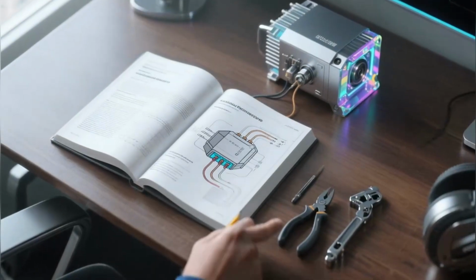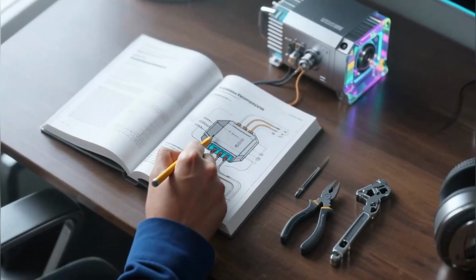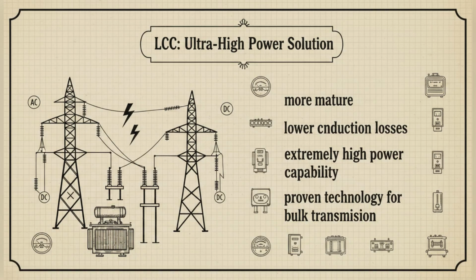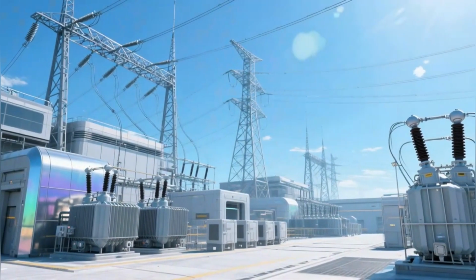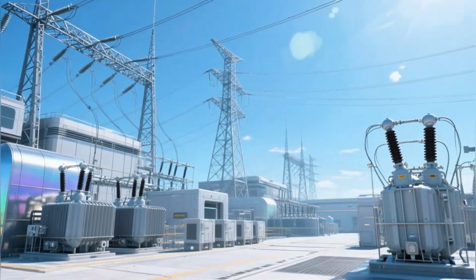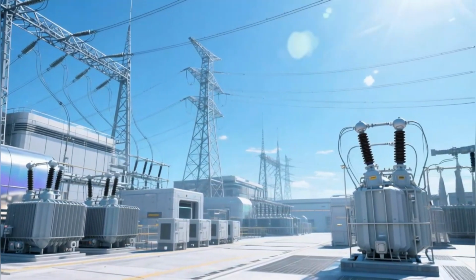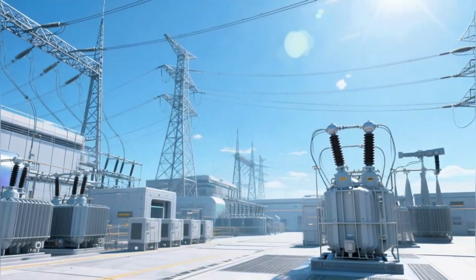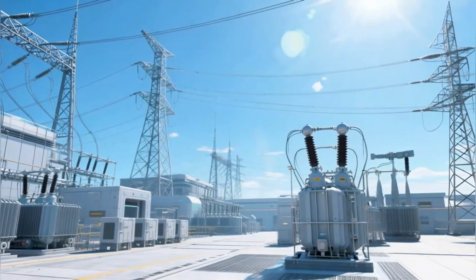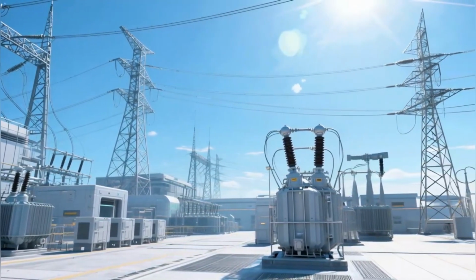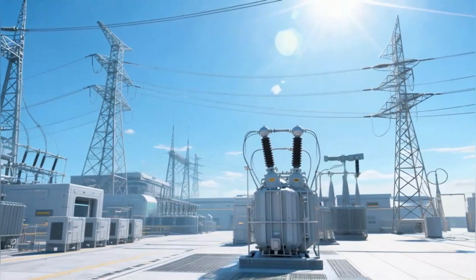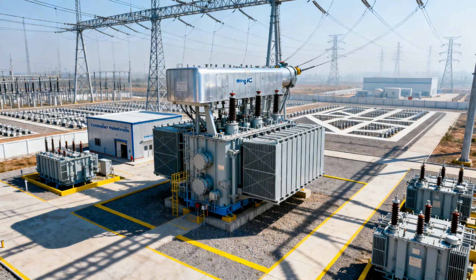The system is based on line commutated converters, LCC. Why LCC? Because at ultra-high power levels, LCC is more mature. Lower conduction losses. Extremely high power capability. Proven technology for bulk transmission. However, LCC requires strong AC grids, reactive power compensation, large harmonic filters. Each converter station includes thyristor valve halls, converter transformers, smoothing reactors, DC filters, AC harmonic filters, reactive compensation banks. The scale of infrastructure is massive.